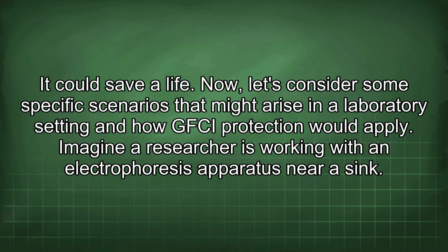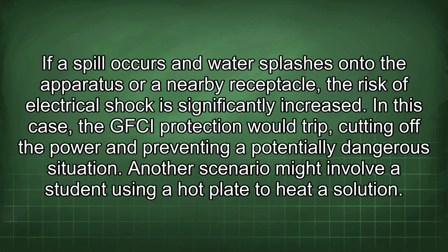Now let's consider some specific scenarios that might arise in a laboratory setting and how GFCI protection would apply. Imagine a researcher is working with an electrophoresis apparatus near a sink. If a spill occurs and water splashes onto the apparatus or a nearby receptacle, the risk of electrical shock is significantly increased. In this case, the GFCI protection would trip, cutting off the power and preventing a potentially dangerous situation.